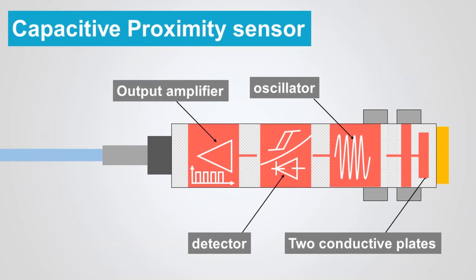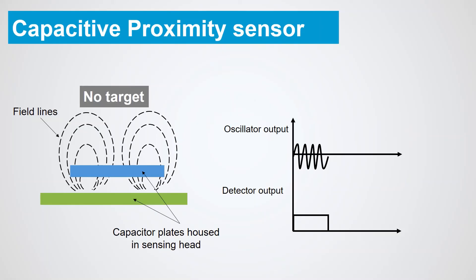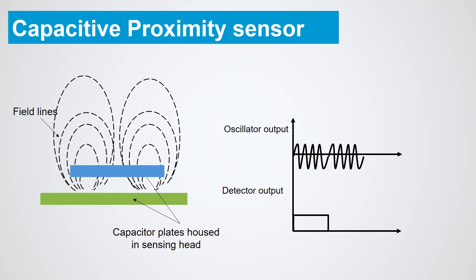In capacitive sensors, two conduction plates at different potentials are housed in the sensing head and positioned to operate as an open capacitor. Air acts as an insulator; at rest, there is little capacitance between the two plates. Like inductive sensors, these plates are linked to an oscillator, a Schmitt trigger, and an output amplifier. As a target enters the sensing zone, the capacitance of the two plates increases, causing oscillator amplitude change, in turn changing the Schmitt trigger state, and creating an output signal.